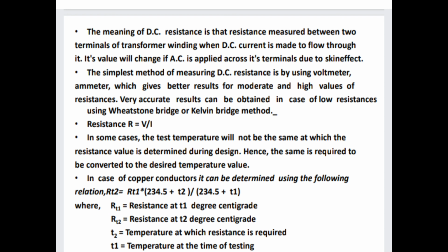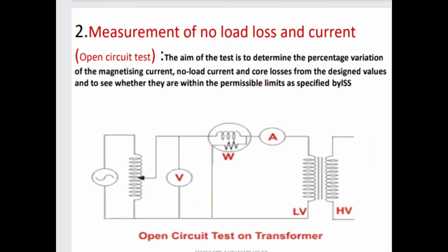So resistance R is equal to V by I, and in some cases the test temperature will not be the same as that at which the resistance value is determined during design. Hence it is required to be converted to the desired temperature value. In case of copper conductor, it can be determined using the following relation. Next is measurement of no load loss and current. So the open circuit test, then the short circuit test, we will see in the next lecture and also explain it.